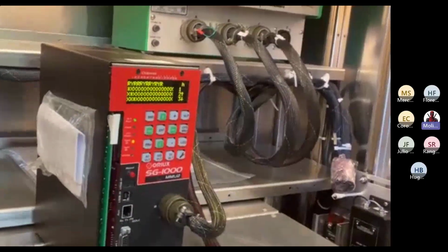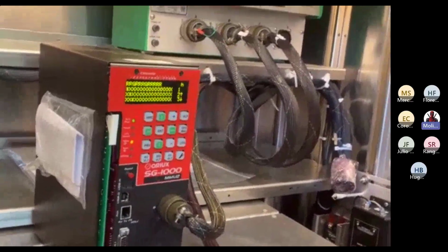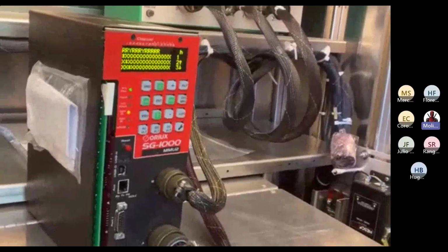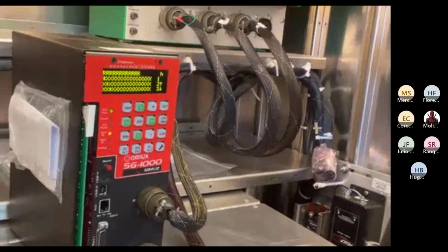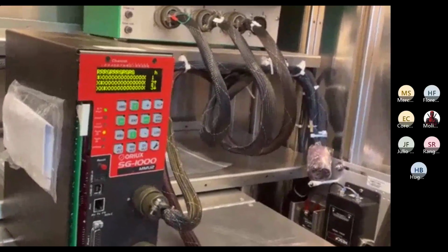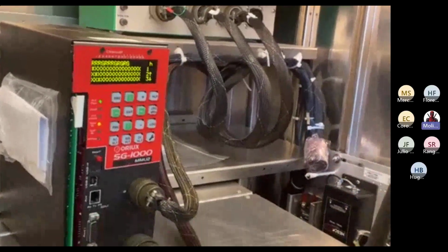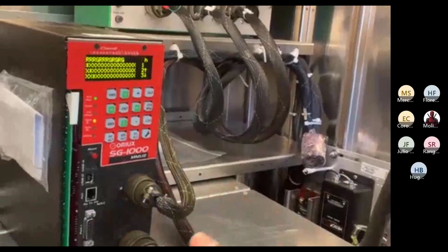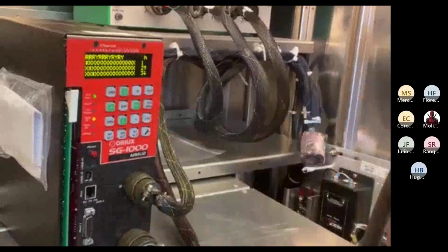No, it'll just show that it's empty, and it'll fail, because as soon as two phases come on together, it'll give you a conflict error immediately. That's different, because nothing's jumpered. I know the other one does that. So say my startup phase is 2 and 6, and I put a blank card up there, that screen is going to tell me my problem is at 2 and 6.